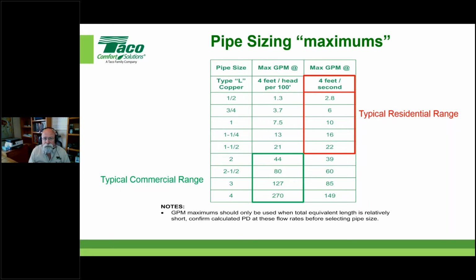Right. And oversizing the system pipe, oversizing the header, is actually a good thing. It simply aids in hydraulic isolation. It does on that close near boiler header for multiple zoning. Absolutely, that's your near boiler piping secondary header, and it wants to be generously sized or copiously sized, however you want to say it. Well, they can be like me, short and fat. Yeah.